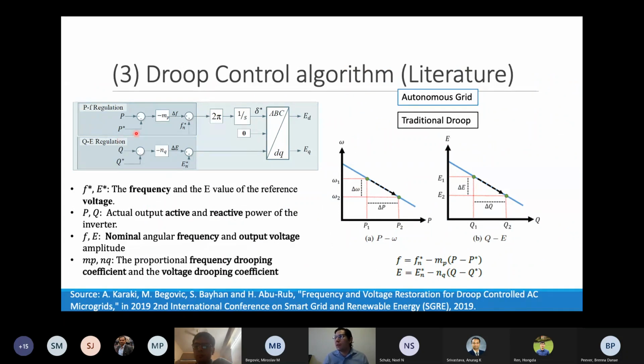The droop control algorithm implemented. The droop control basically helps us work in an autonomous grid, and also in a multi-inverter grid that is not connected to the main grid. So our droop control will help us share the load between the different connected inverters, and to do it without having communication to every single one of the inverters. In this case, we can prove that when we introduce new active power, we have a drop in the omega, and when we introduce new reactive power, we have a drop in the voltage reference.